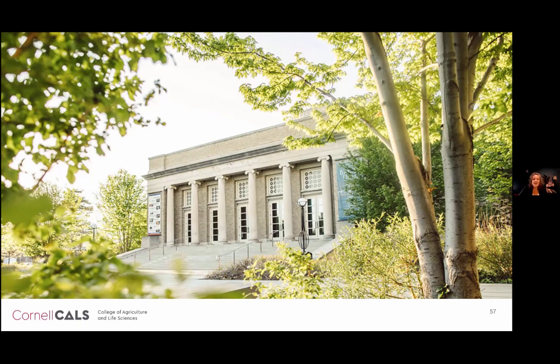Yeah, great question. So most somatic cell counting is done with a technique called flow cytometry. You might have heard of a Bactoscan before. And essentially what happens is the somatic cells are fed through a very fine capillary tube. And as they are fed through that tube, they line up individually in a row. And then as they move through that capillary tube, they move past a laser, and that counts the somatic cells. So it's a very, very fast technique. It can be done in a couple of minutes. So you get quick turnaround.